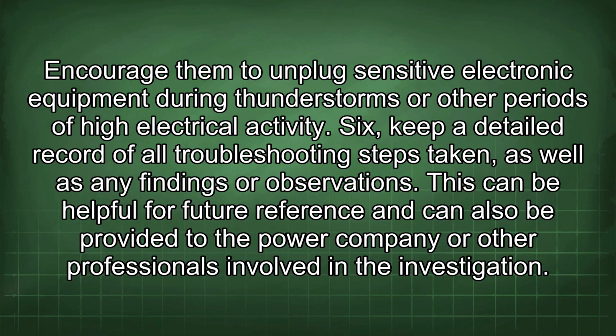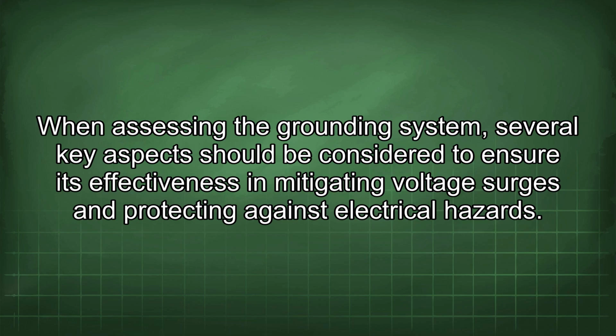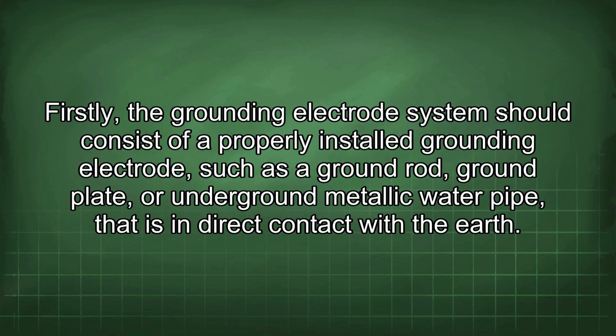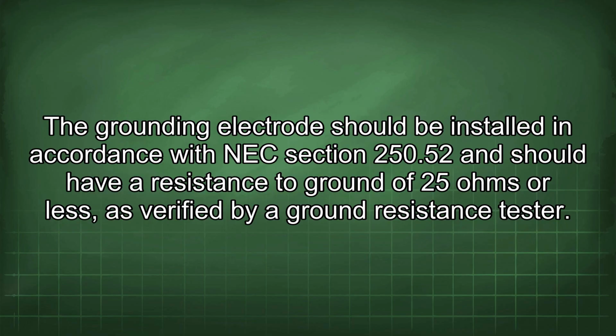in the investigation. When assessing the grounding system, several key aspects should be considered to ensure its effectiveness in mitigating voltage surges and protecting against electrical hazards. Firstly, the grounding electrode system should consist of a properly installed grounding electrode, such as a ground rod, ground plate, or underground metallic water pipe that is in direct contact with the earth. The grounding electrode should be installed in accordance with NEC section 250.52 and should have a resistance to ground of 25 ohms or less, as verified by a ground resistance tester.